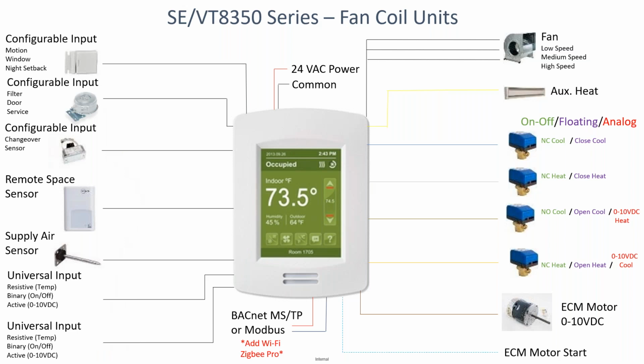I just want to show one picture here of maybe a way a fan coil would be wired up, right? So from the device itself, you can do the configurable inputs, either for windows or motion, dirty filter, door, general service alarm, changeover sensor. It's got an input for remote space sensor. So let's say it's a retail establishment where they have the controller in the manager's office, but the actual temperature is being measured someplace else. That can be a wired or a wireless connection to it. It's got the supply air sensor already. It's got the fan, which can be low, medium, or high speed, or ECM motor. It's got an output for auxiliary heat, and then you configure for on-off, floating, or modulating outputs for that controller.